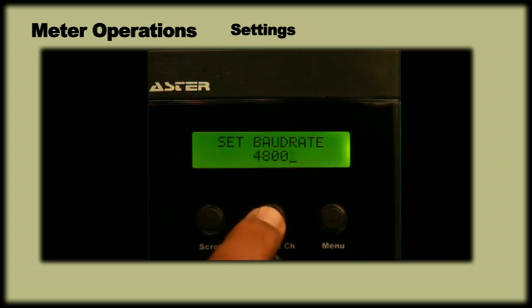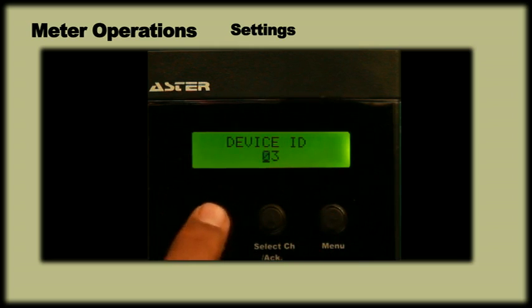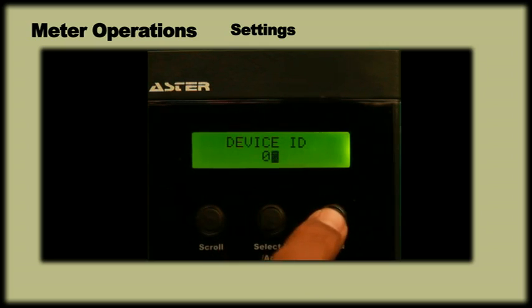Once you have selected the desired baud rate, press menu key and the display will ask for device address. Use scroll and select ch keys to set the device address to the required address. Press menu twice to save and exit.